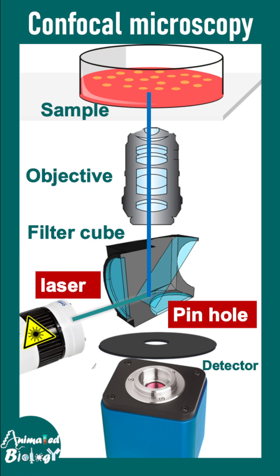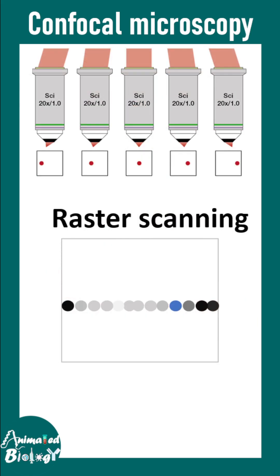Here is the light path of a confocal microscope. The laser goes through a filter cube, travels through the objective, and illuminates the fluorescent specimen. Light from the specimen travels back past the dichroic mirror and past the emission filter. Before it reaches the detector, it hits the pinhole, where all out-of-focus light is cancelled.